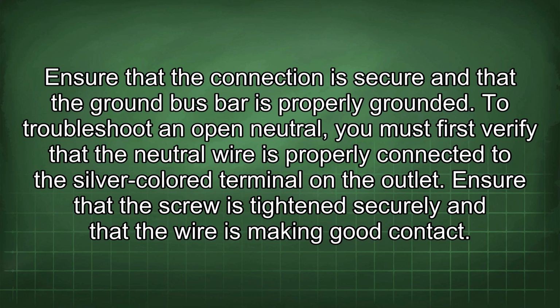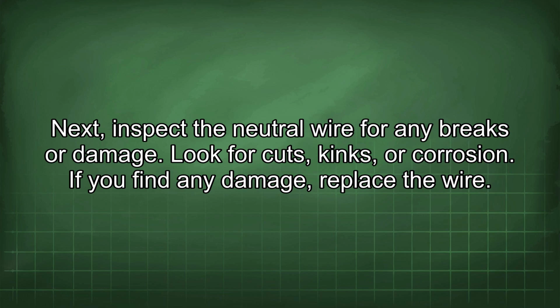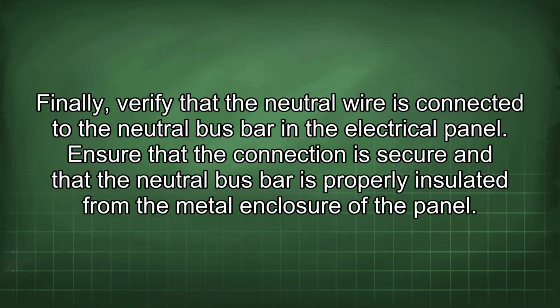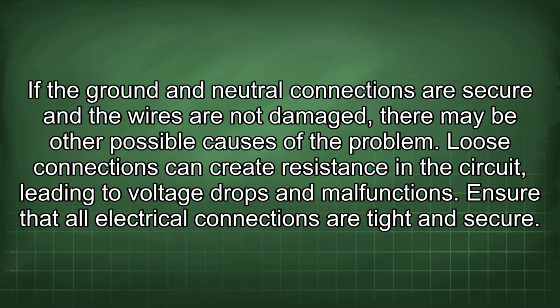To troubleshoot an open neutral, you must first verify that the neutral wire is properly connected to the silver-colored terminal on the outlet. Ensure that the screw is tightened securely and that the wire is making good contact. Next, inspect the neutral wire for any breaks or damage. Look for cuts, kinks, or corrosion. If you find any damage, replace the wire. Finally, verify that the neutral wire is connected to the neutral bus bar in the electrical panel. Ensure that the connection is secure and that the neutral bus bar is properly insulated from the metal enclosure of the panel. If the ground and neutral connections are secure and the wires are not damaged, there may be other possible causes of the problem.